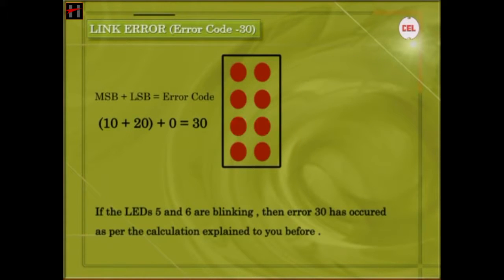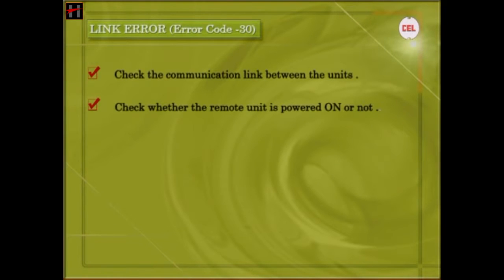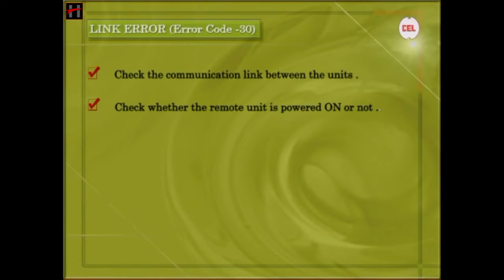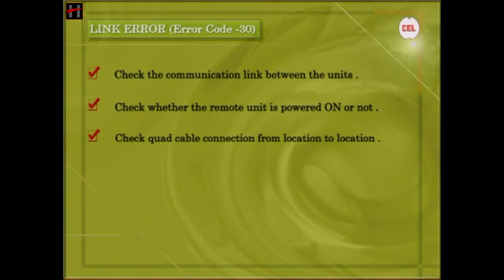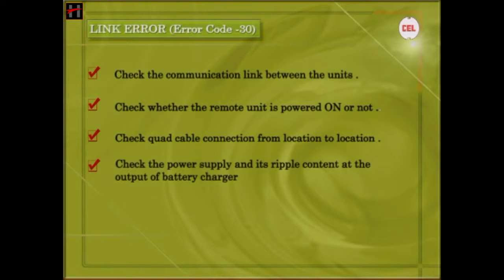In order to rectify the error, carry out the following checks: 1. Check the communication link between the units. 2. Check whether the remote unit is powered on or not. 3. Check for quad cable connection from location to location. 4. Check the power supply and its ripple content at the output of the battery charger.